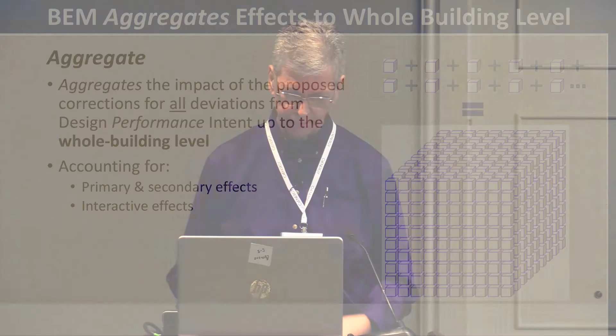In addition to what I call interactive effects, there's something worth distinguishing called secondary effects. So the example here: consider that we've got something to do with lighting controls. Lighting controls - if we dim the lights or get them to turn off more than they should have, or perform more effectively - presumably there's going to be reduced primary direct energy on that. It's going to reduce the internal gain, and from that there will be decreased cooling requirements, right? So there'll be a cooling benefit, but likewise a heating or reheat penalty, and all of that again will come under the guise or influence of interaction with the electric rate or whatever the utility types are.